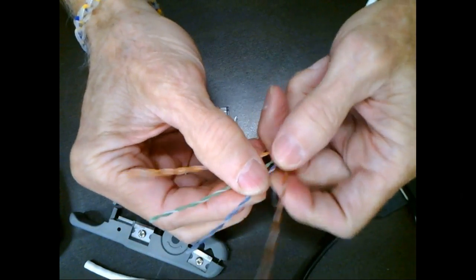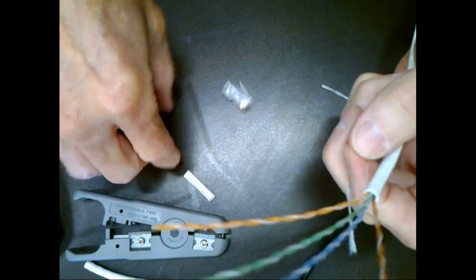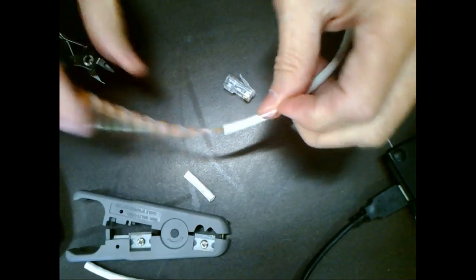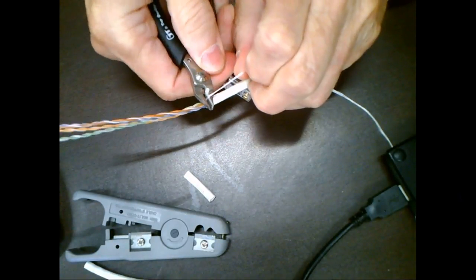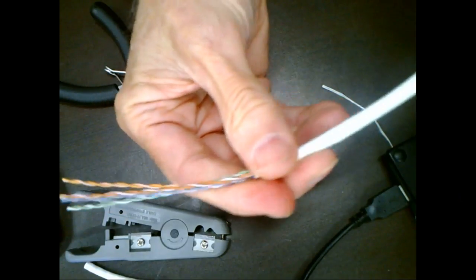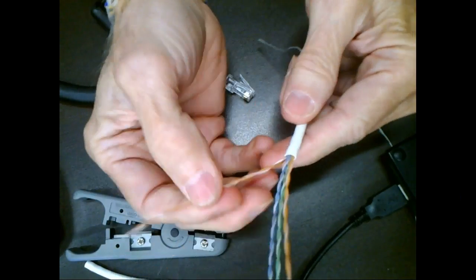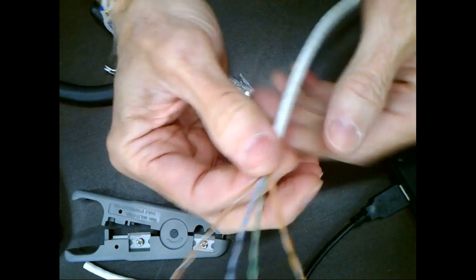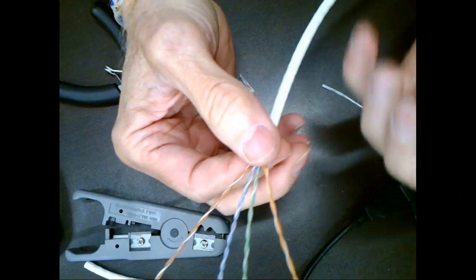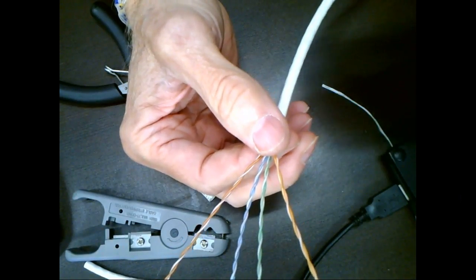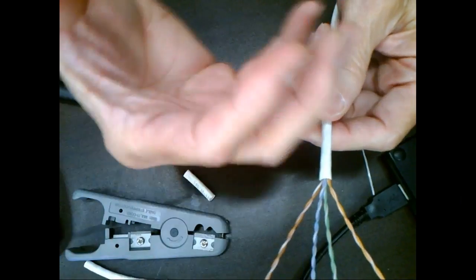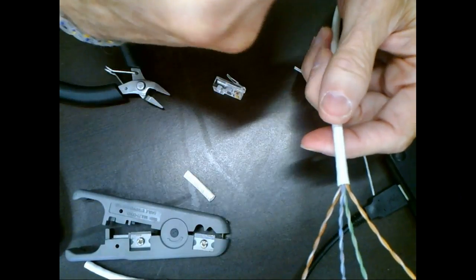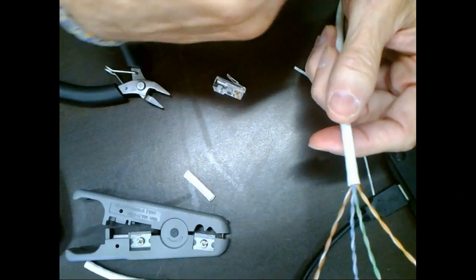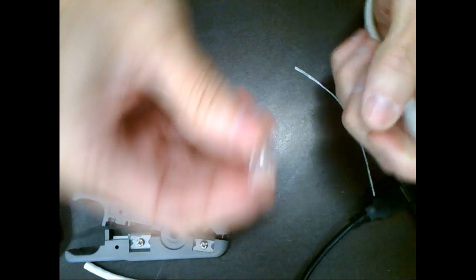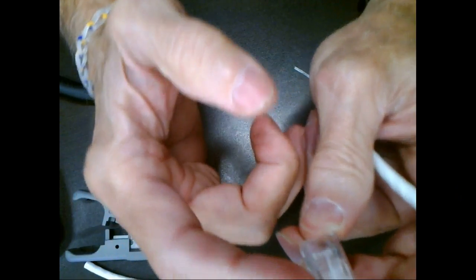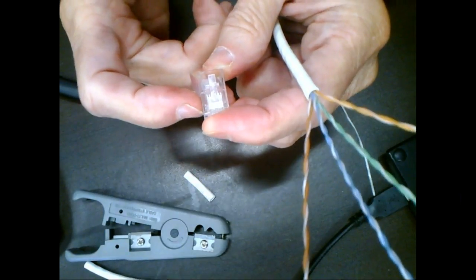Now, once we get it stripped, of course, we'll cut off the strength member flush with the insulation. Now, we're using what we call UTP cable. This is what we use in commercial applications and home applications, which is unshielded twisted pair cable. We have another one, which is what y'all are using, that green cable. It's called STP. What do you think STP stands for? Shielded twisted pair. So in manufacturing and industrial applications where you have a lot of electromagnetic interference, you'll need to use STP cable. And on the STP cable, you'll have a metal jacket that comes all the way out to about here where it snaps in.